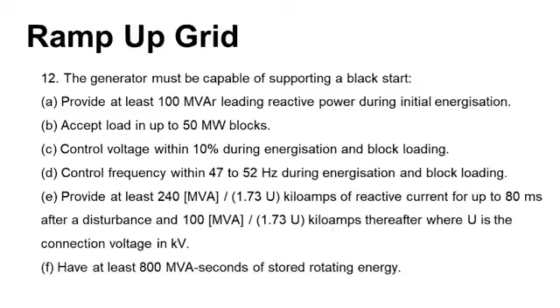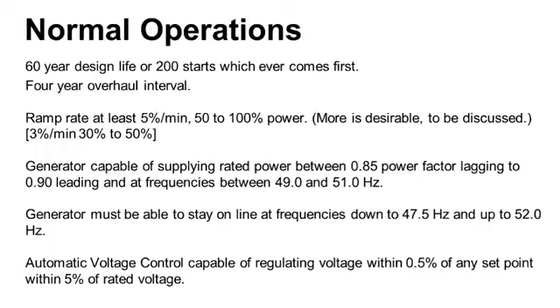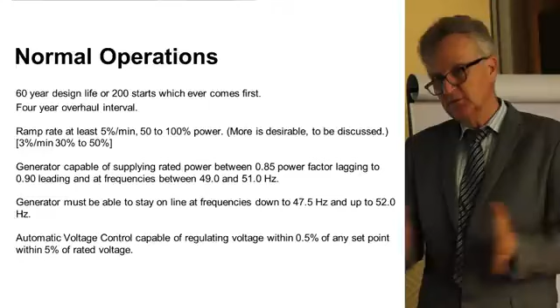And then when you want to ramp up to power up the grid, we have to be sure that our control system understands that you are bringing up the grid so that we widen the window of what is acceptable behavior. We're speccing right now 60-year design life or 200 starts. I want to push that up to 80-year design life. I think there should be no problem with that. 4-year overhaul for turbines. Typical is 3. We're pushing a little further so it coincides with when we're changing the cans.